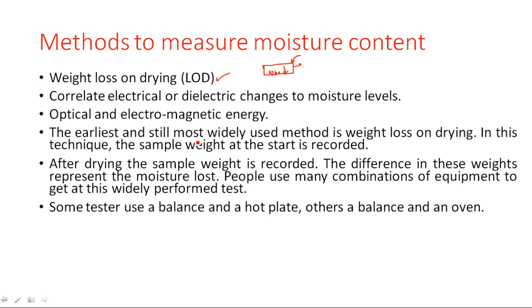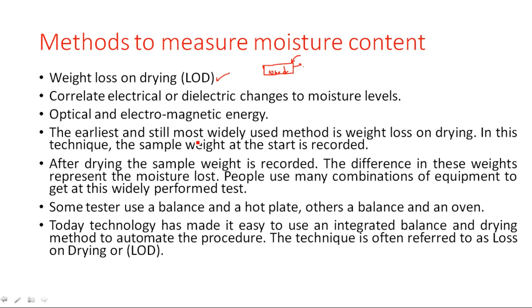Today, technology has made it easy to use an integrated balance and drying method to automate the procedure. This technique is often referred to as Loss on Drying, or LOD. What we are losing here is weight — loss of weight after drying. That is LOD: Loss on Drying.